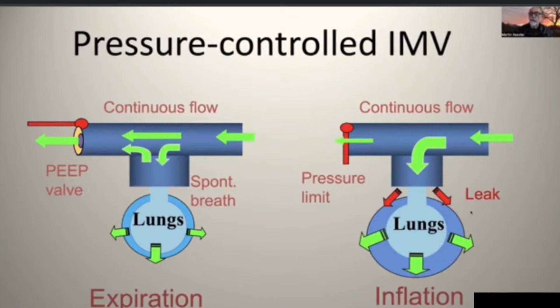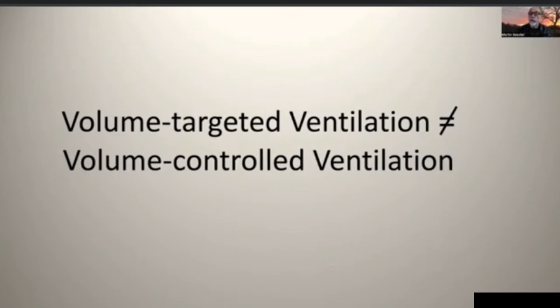So along came volume-targeted ventilation, which is not the same thing as volume-controlled ventilation. Volume-targeted ventilation, as I use the term, is pressure-controlled ventilation with volume targeting, which occurs by automatic adjustment of inflation pressure in order to maintain a stable tidal volume. So as opposed to making those changes manually, the ventilator makes these automatically and in real time, leading to more rapid weaning from mechanical ventilation and avoidance of lung injury.